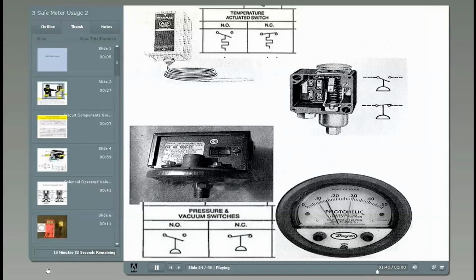The normally open NO contact will close at the selected pressure, and the normally closed NC contact will open at the selected pressure. This is a very good device to have in a plant to automatically control the damper. It provides very important control, inexpensively.